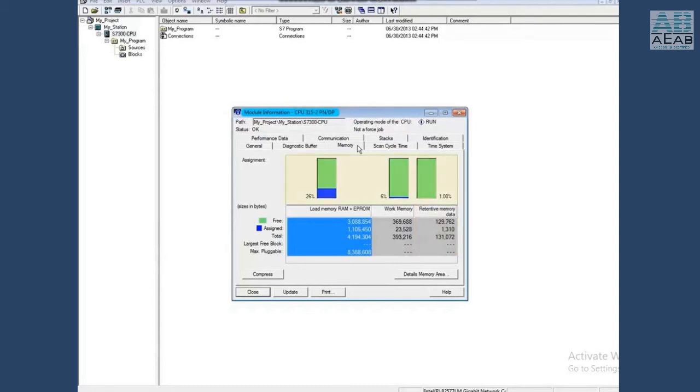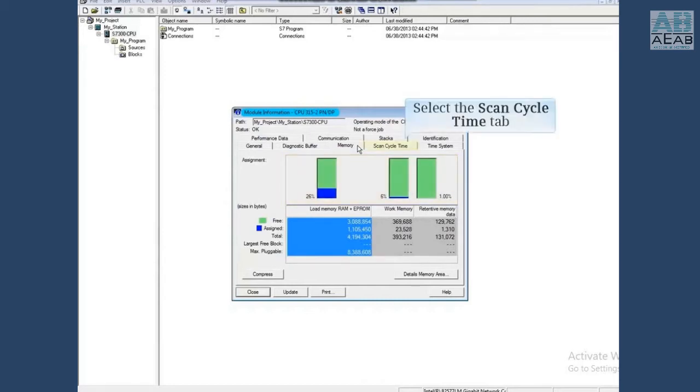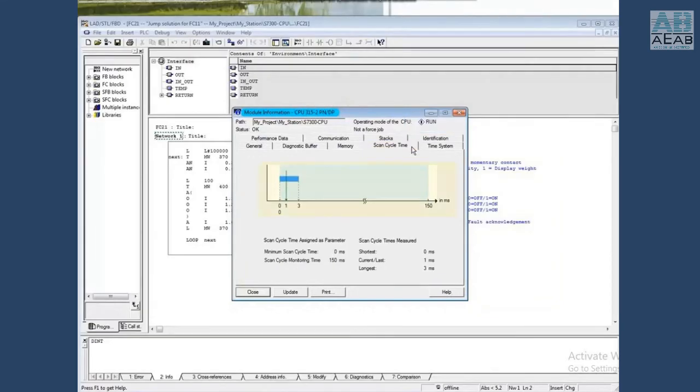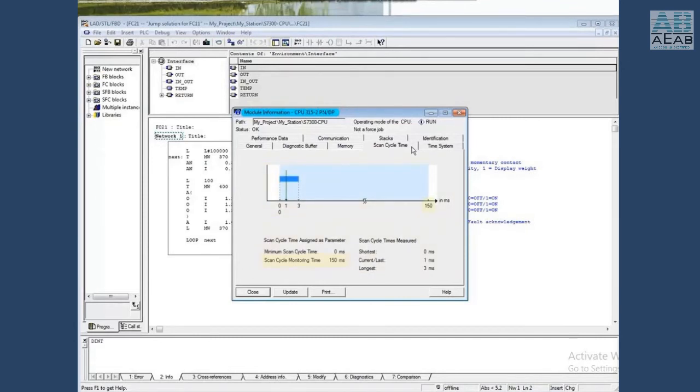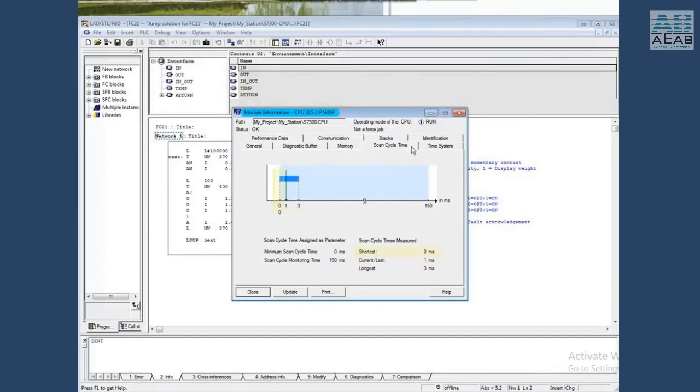These fields are shown graphically in the assignment section of the window. Click on the scan cycle time tab. This tab shows both graphically and in words the watchdog cycle time, which is 150 milliseconds, the longest scan cycle so far, which is 3 milliseconds, the shortest scan cycle, which is 0 milliseconds, and the current scan cycle, which is 1 millisecond.